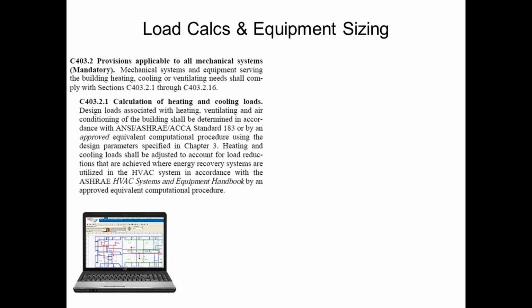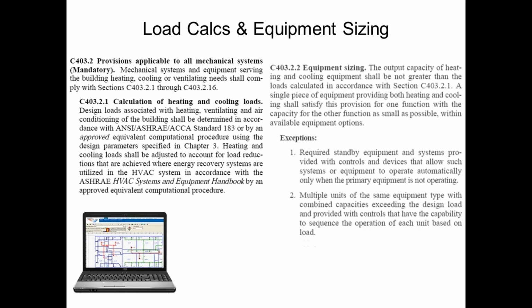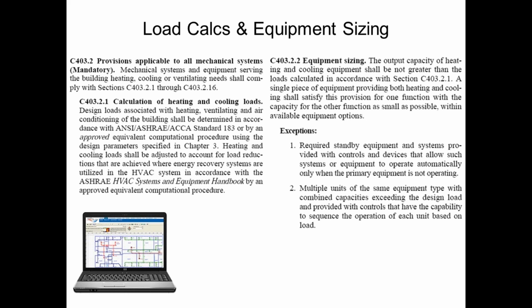So you do need to do a load calculation in compliance with ASHRAE Standard 183 or something very similar to that you can get approved. But your normal load calculation programs like Trace and HAP and DOE and these things will be able to comply without any difficulty. So you need to do a load calculation, and then you size your actual equipment to match that load. The way that this is written, you're actually not allowed to oversize the equipment at all. So the heating and cooling equipment shall not be greater than the loads calculated.